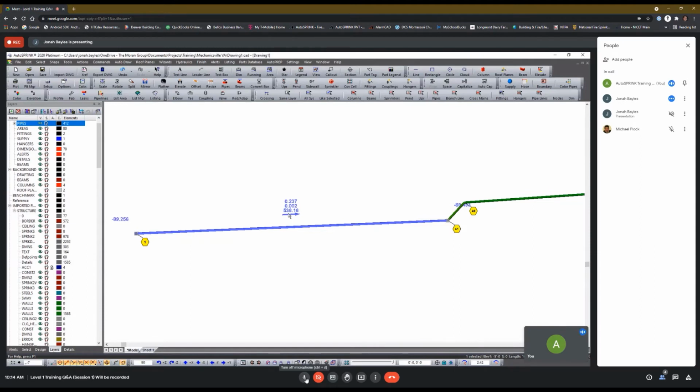The value just above that is your calculated pressure loss per foot value. The value on top of that is the total pressure loss through that selected pipe segment. So the value on the right end of that pipe minus the top value in the middle should equal the value on the left end of the pipe.